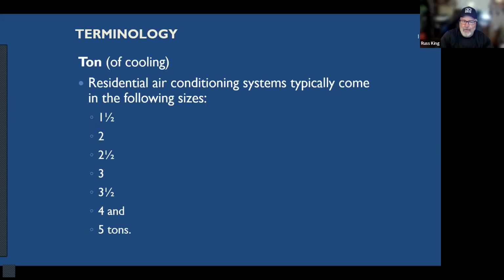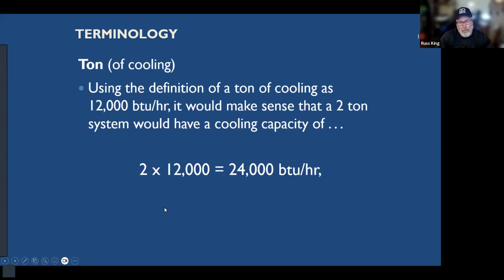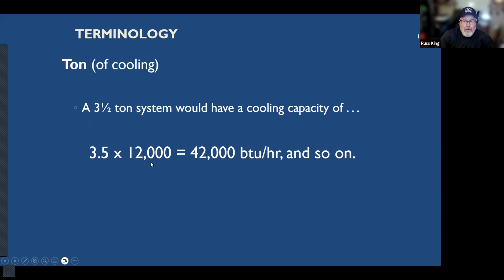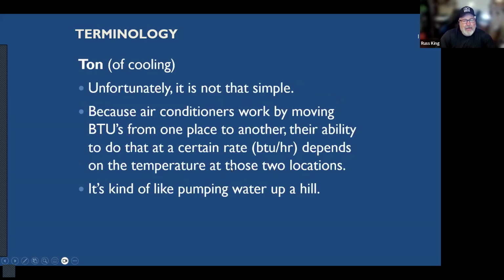If you go look at a typical house and look at the condenser, it's probably going to be one of these. And the way you figure out how many tons an air conditioner is, you take the tonnage and multiply it times 12,000, and you get this number. They will typically hide a little code in the model number of the air conditioner, and you can figure out what the tonnage is by using this equation. So typically a 2-ton air conditioner will have about 24,000 BTUs. A 3.5 ton air conditioner will have about 42,000 BTUs. Okay, but it's not that simple.